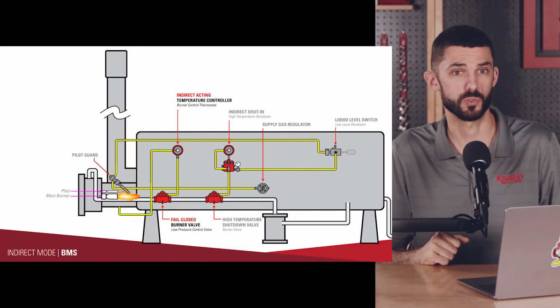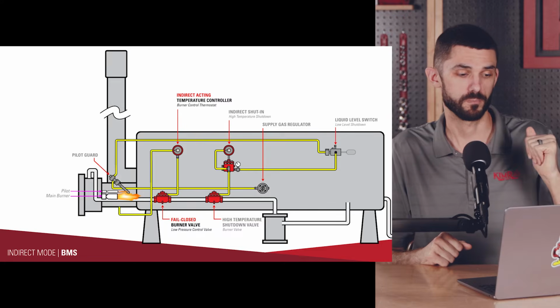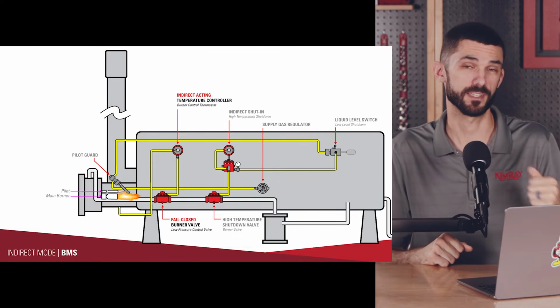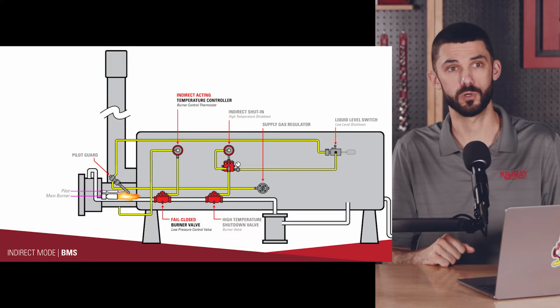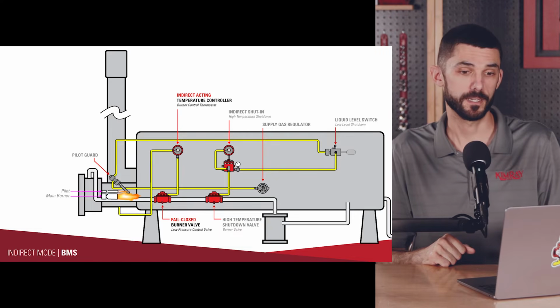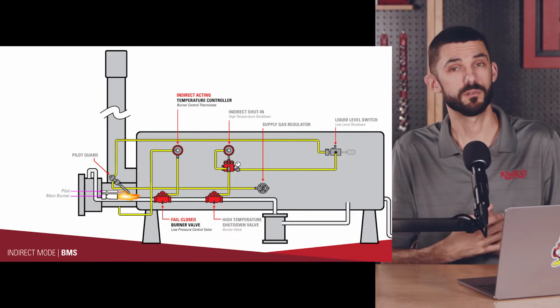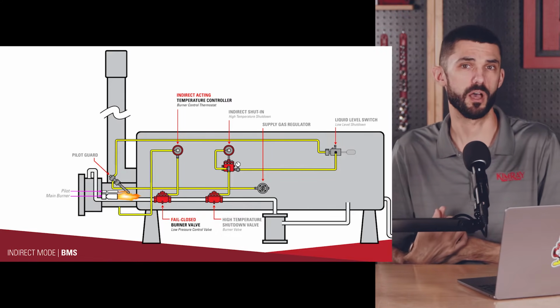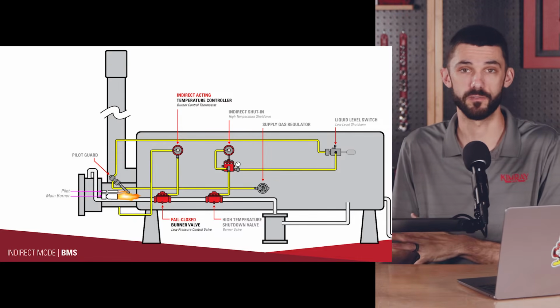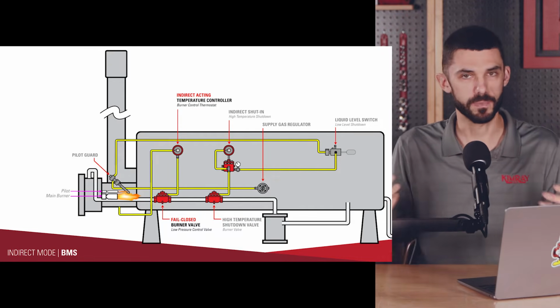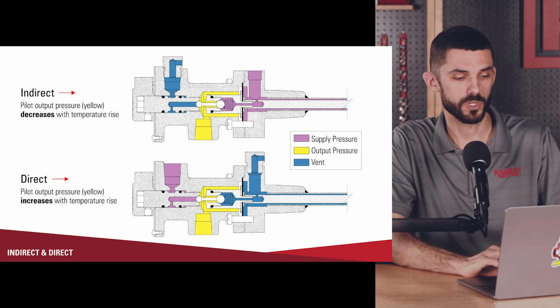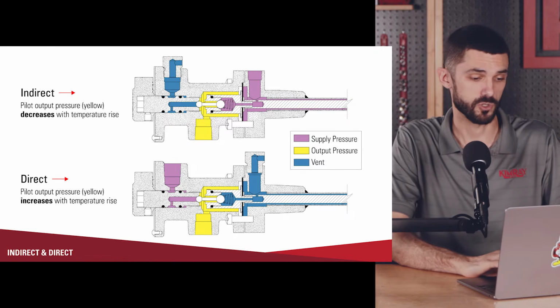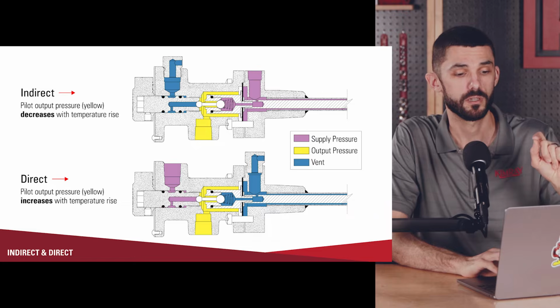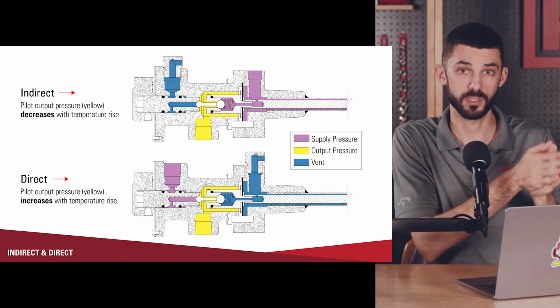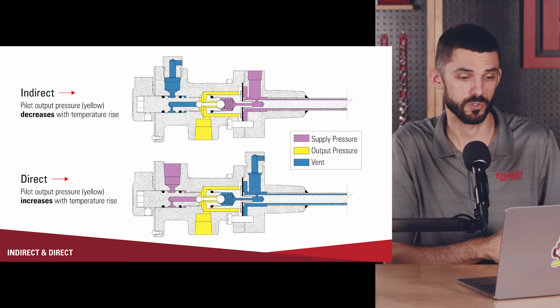In other applications where you have high temperature shutdowns and things like that, that is most typically going to be an indirect acting as well. Again, depending on the failure position of the valve it's working with. So just keep that in mind. But any switch between direct and indirect acting, it's just about where the supply is coming into the controller.